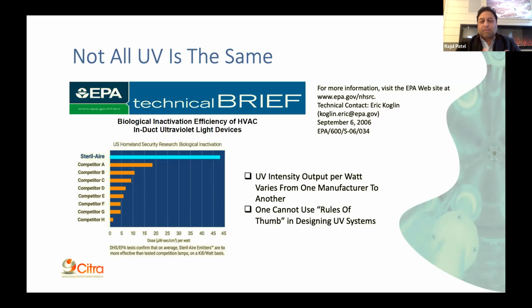We've found that salespeople, who may not be technical, are trained with rules of thumb to make things easy, either saying you need X amount of wattage per coil size, or per coil size you need a certain number of UV emitters. That's not the way the design actually works.